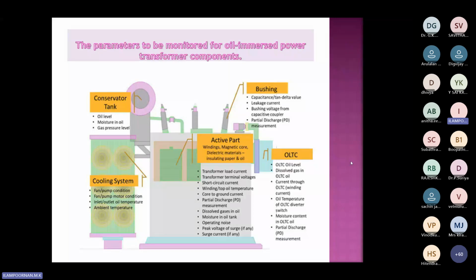Okay. So the thing is, you will have expansion of the oil, and if you are tightly packing the transformer, what will happen? If the oil expands, expansion can't take place, or otherwise the tank will burst. So they provide a separate conservator tank where space for oil expansion is provided. Expansion will happen in the conservator tank, whereas the transformer main tank will be full of oil. Clear?